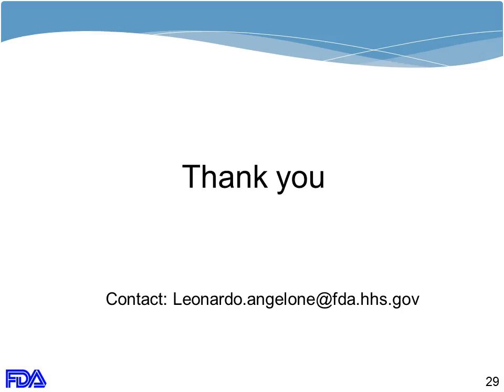Up to 2010, there were no pacemakers that were approved by the FDA for the market with an MR labeling. So patients with pacemakers were not approved to undergo MRI by the FDA, here in the U.S. The first pacemaker that received MR labeling was the Medtronic Revo, and that occurred in 2011.